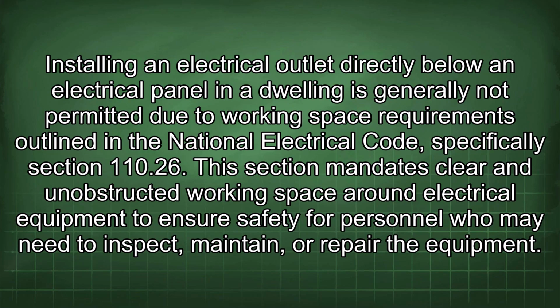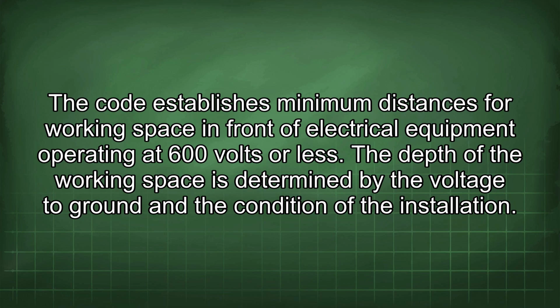Installing an electrical outlet directly below an electrical panel in a dwelling is generally not permitted due to working space requirements outlined in the National Electrical Code, specifically Section 110.26. This section mandates clear and unobstructed working space around electrical equipment to ensure safety for personnel who may need to inspect, maintain, or repair the equipment. The code establishes minimum distances for working space in front of electrical equipment operating at 600 volts or less. The depth of the working space is determined by the voltage to ground and the condition of the installation.